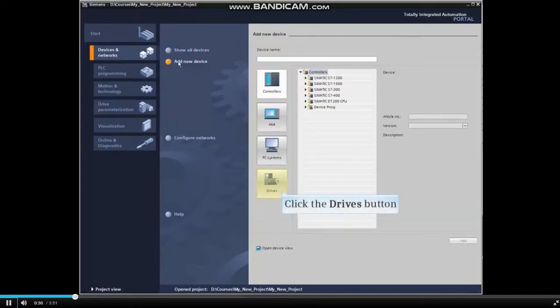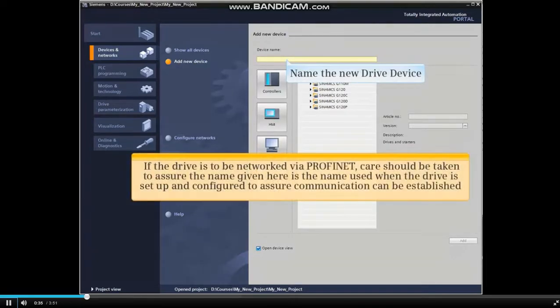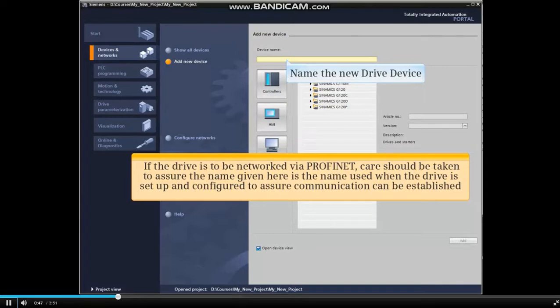Click the Drives button and name the new drive device. If the drive is to be networked via Profinet, care should be taken to assure the name given here is the name that will be used when the drive is set up and configured to assure communication can be established.